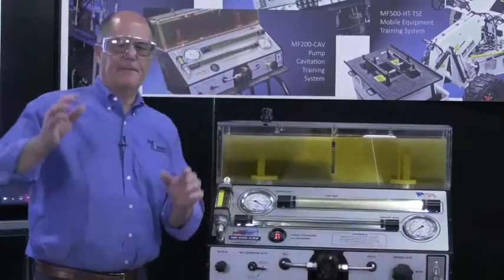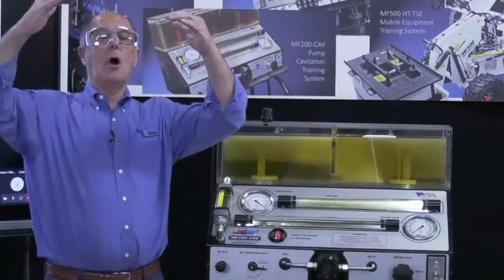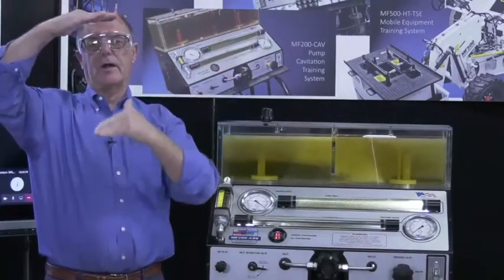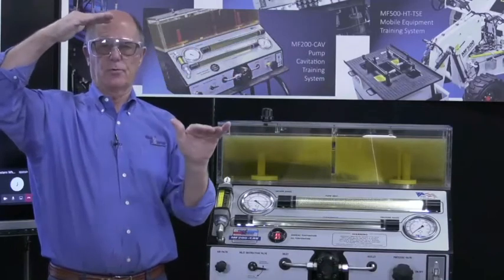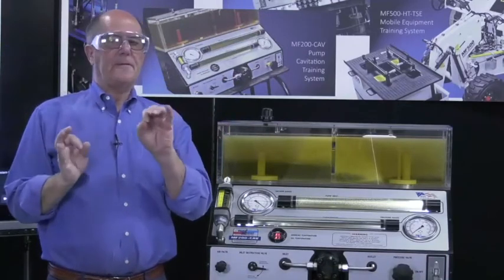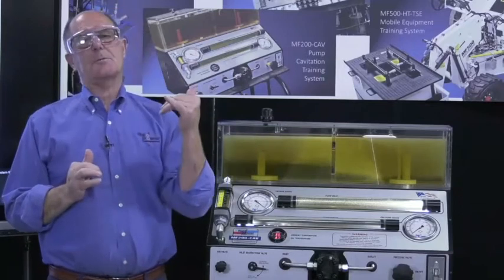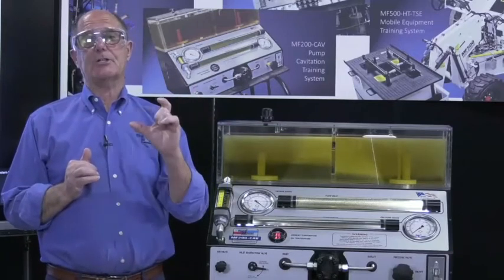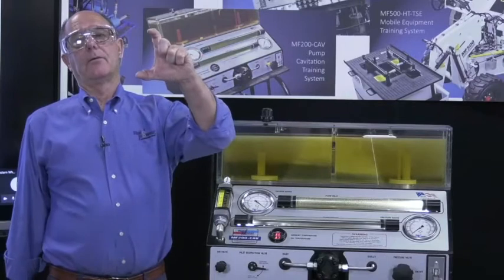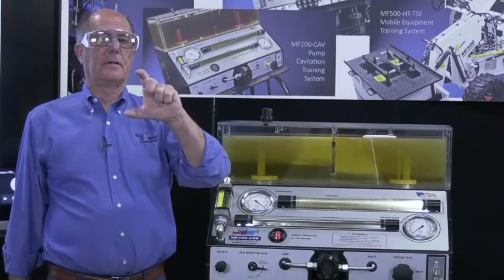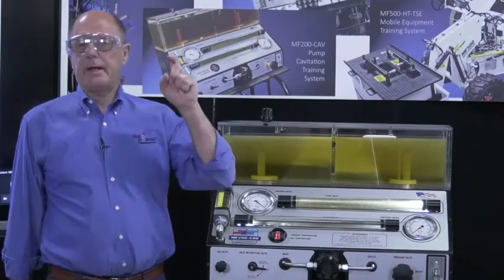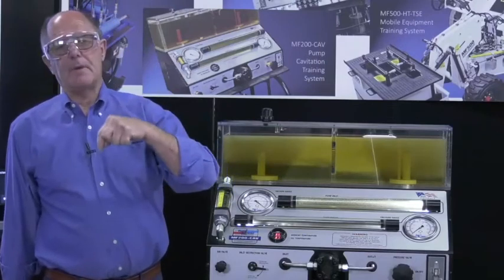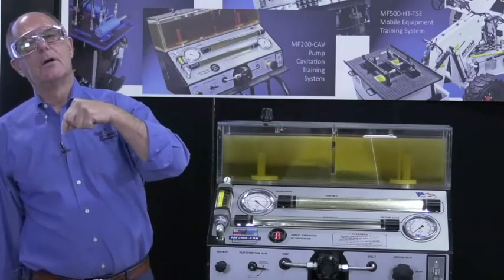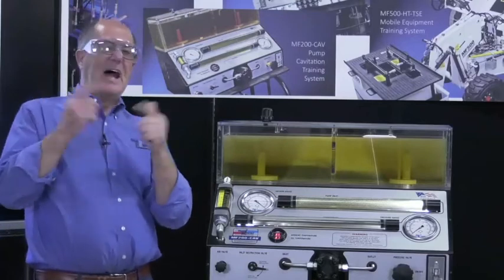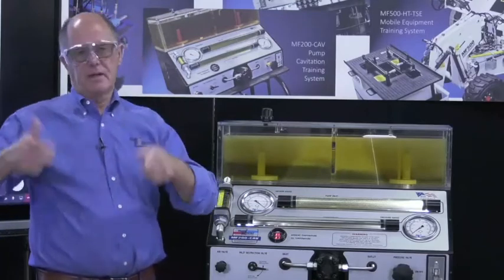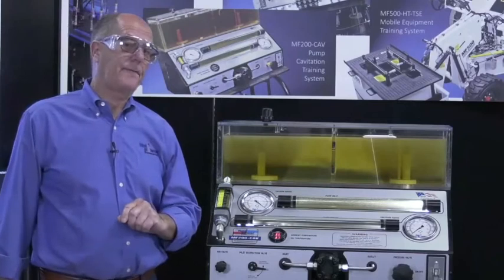All right. Now, finally, what happens if, by rule of thumb, there should be no return line dropping oil in on top of oil? It's against the rules. Some manufacturers are so bent on keeping case pressures down on pumps and motors that they will actually drop the oil return lines in above the oil level. You can't have any flowing lines putting oil in above the oil level because for the life of the machine, it will just perpetuate air. Let me demonstrate that for you.